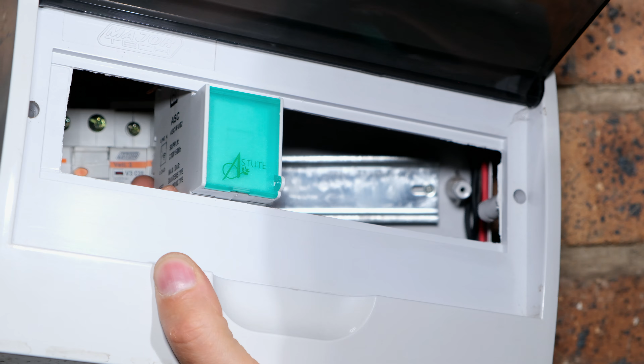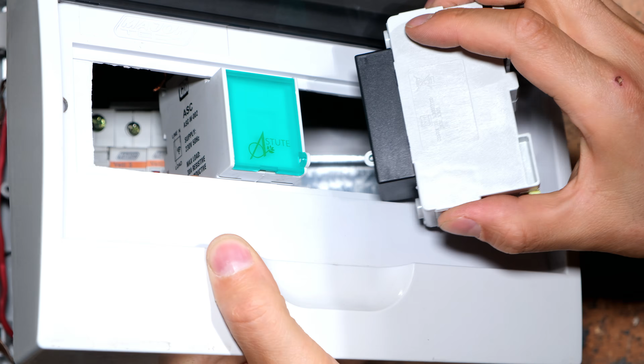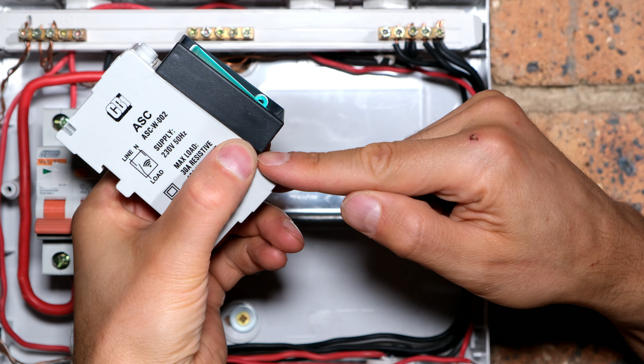I'm now going to insert the timer. Now notice that the timer has this black plastic around it. Now this depends on the size of the cover of your distribution board. Notice that for this one, I've removed the black cover and it can fit through. This one, which still has the black cover, cannot fit through, which means I have to remove the black cover in order to get it to fit through the cover here. What I do is I just take my nails and I gently separate it, then I flip it, and I make sure to hold that open, and I take my nails and I do the same. Now I can just slide that off.